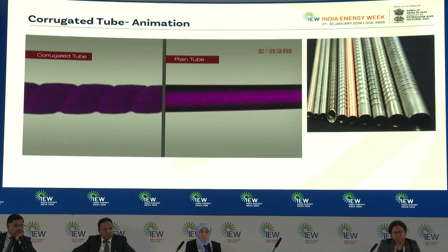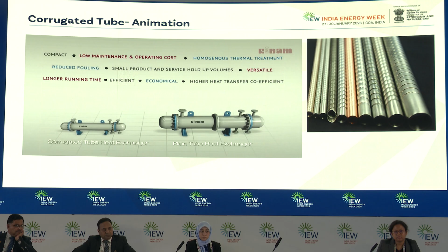Corrugated tubes also offer homogeneous temperature distribution in the tube. The corrugated tube heat exchangers are compact, economical in cost, efficient and versatile with reduced fouling. So what we are trying to do here is combine the advantages of plate heat exchangers and shell and tube heat exchangers in corrugated tube heat exchangers.